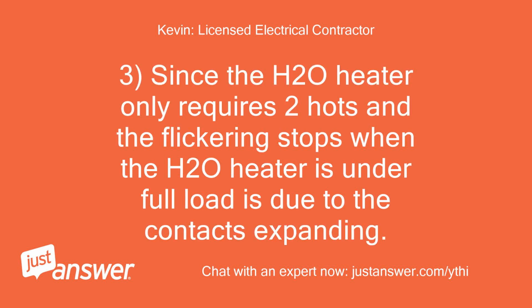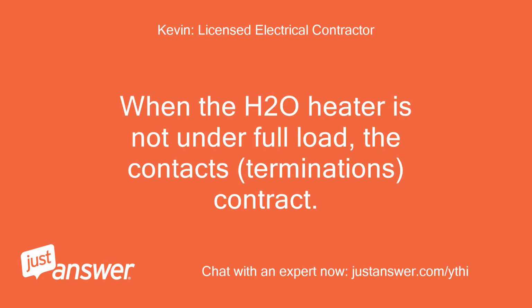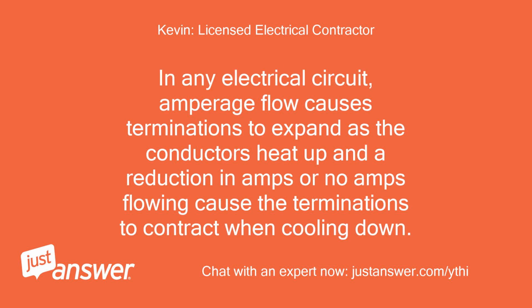3. Since the H2O heater only requires 2 hots and the flickering stops when the H2O heater is under full load, it is due to the contacts expanding. When the H2O heater is not under full load, the contacts, terminations, contract. In any electrical circuit, amperage flow causes terminations to expand as the conductors heat up, and a reduction in amps or no amps flowing cause the terminations to contract when cooling down.